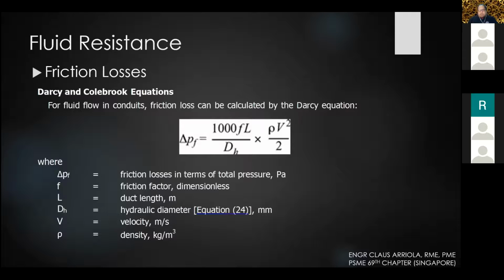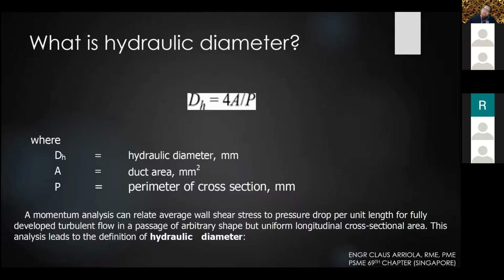Friction losses from the Darcy and Colebrook equation: the friction loss in terms of total pressure is equal to 1,000 times the friction factor times the duct length, divided by the hydraulic diameter, times the density times the velocity squared, divided by 2. But what is the hydraulic diameter? The hydraulic diameter is equal to 4 times the duct area, in millimeters squared, over the perimeter of the cross-section.